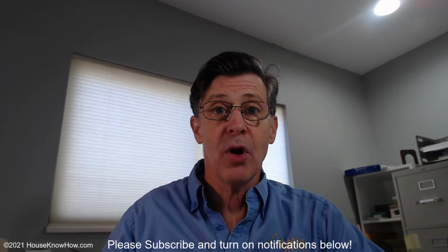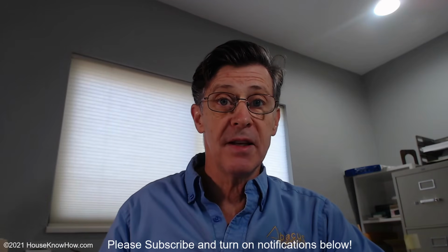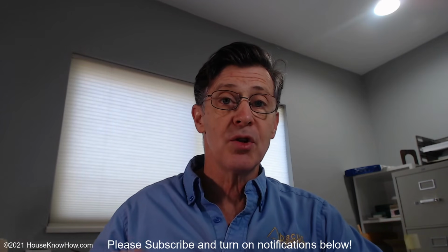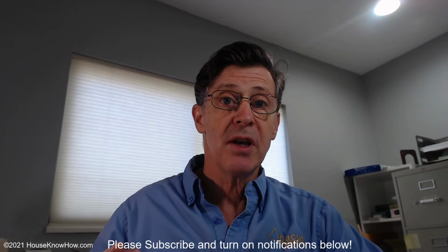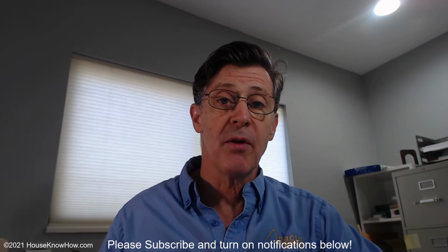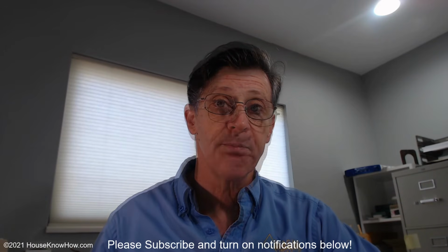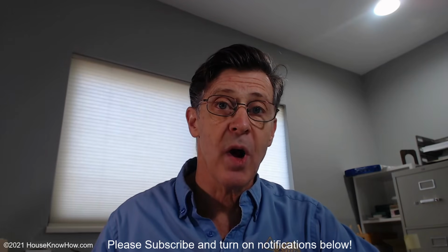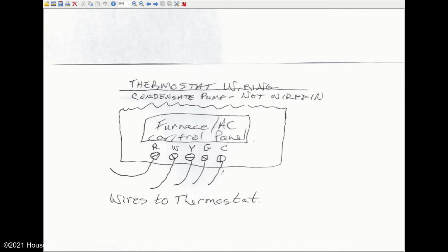To prevent this, all you or an HVAC technician needs to do is to wire these overflow switches into the thermostat wiring of a furnace or air conditioner. Let's take a look at how this wiring is done. This is how a furnace or air conditioner is wired when the condensate pump is not wired in.